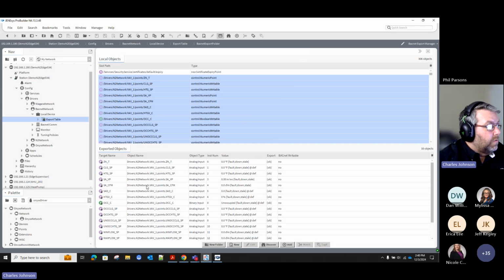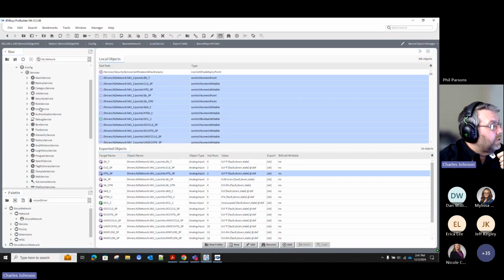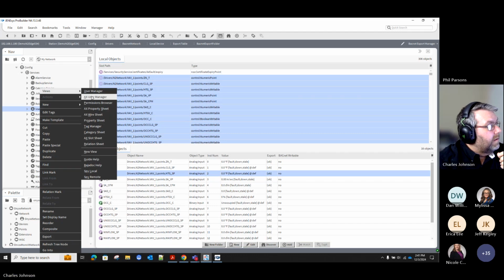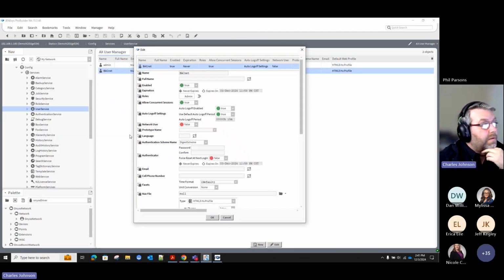Just make sure that when you have things that you want to be written, such as occupancy commands and your set points, make sure that in your user service the BACnet user has admin rights. If you do not have admin rights as a BACnet user, and there's no password—this is created when you add the BACnet network into here—you won't be able to control your set points or scheduling if need be. But as long as it's admin rights, you'll be able to do that.